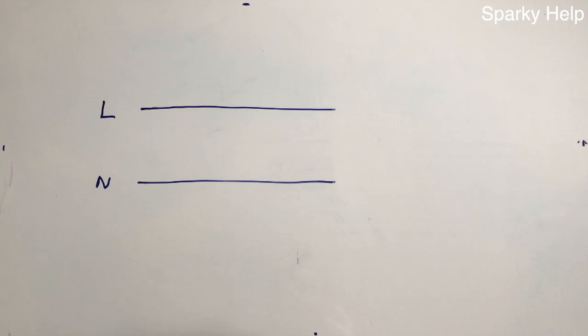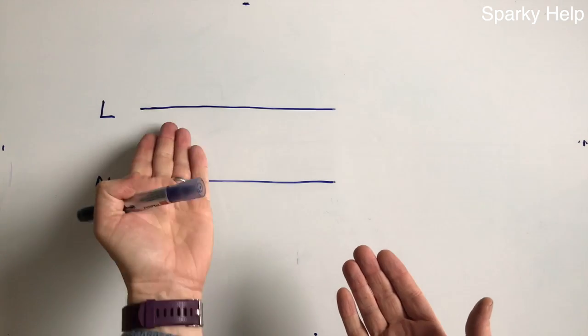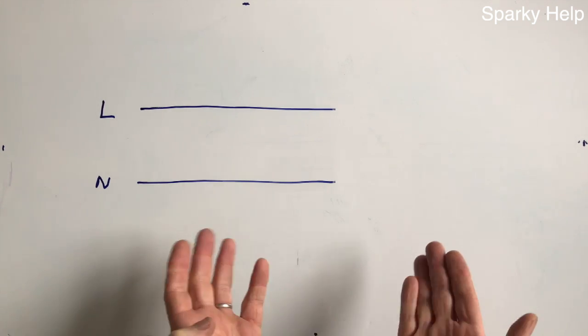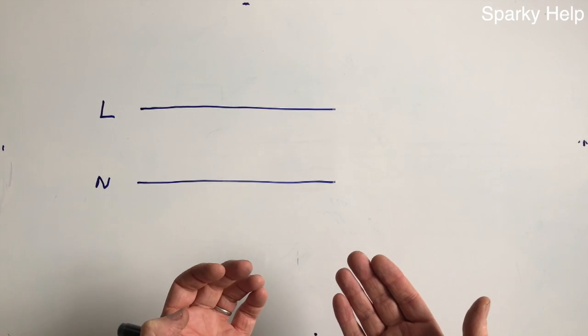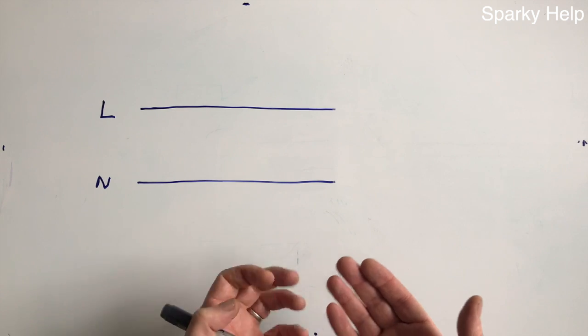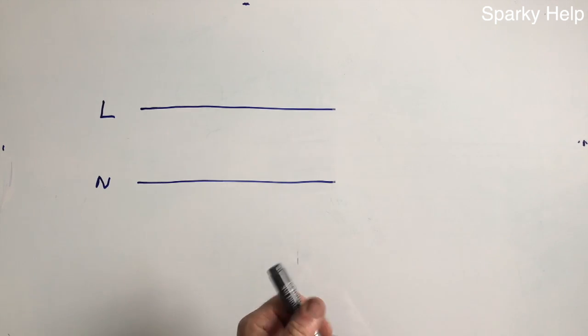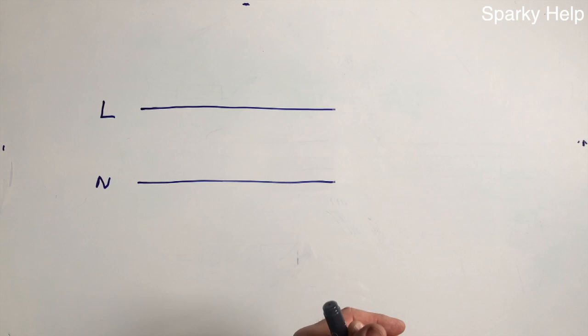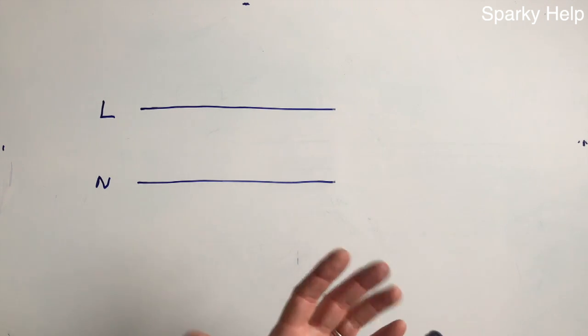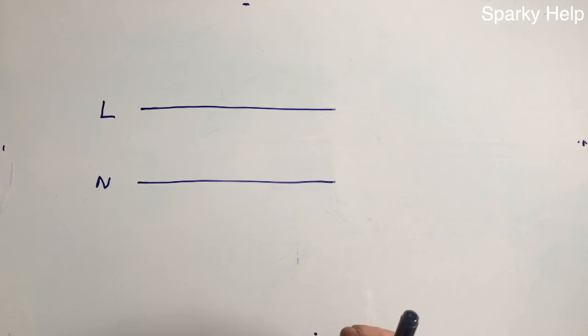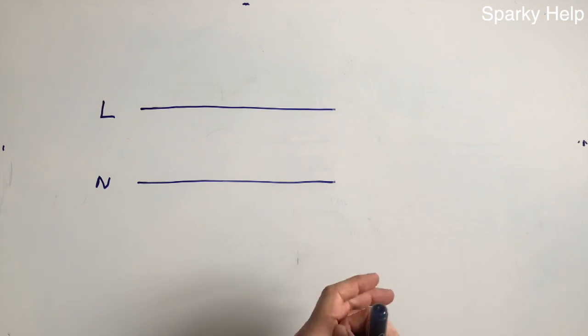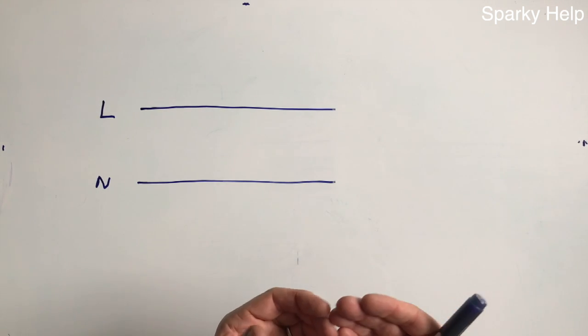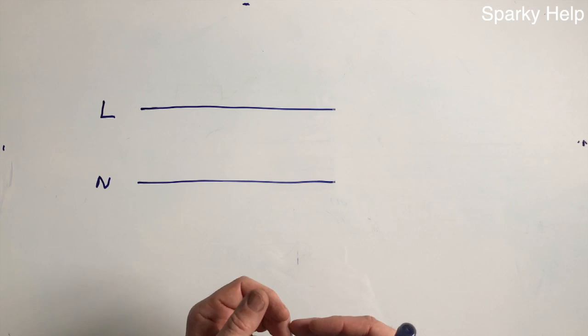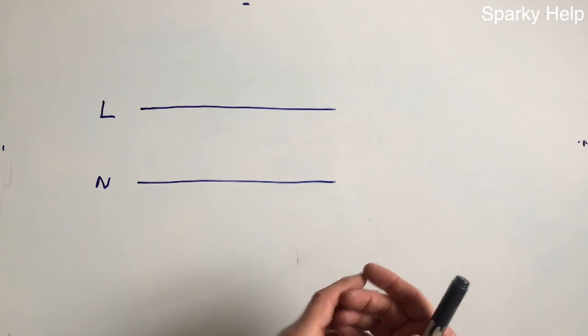So what is insulation resistance? Well, basically it's making sure that the line and neutral are not touching, the line and earth is not touching, and the neutral and earth is not touching. So basically we're going to put a voltage through it, and the voltage we put through it is a nominal 500 volts. Now why 500 volts? Well, think about it logically, it's quite simple really. The voltage we're going to put through the circuit is 230 volts, and therefore we would like to test it at a higher voltage than actually passes through it. Now why 500 and not 300?